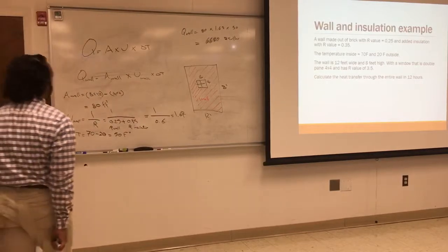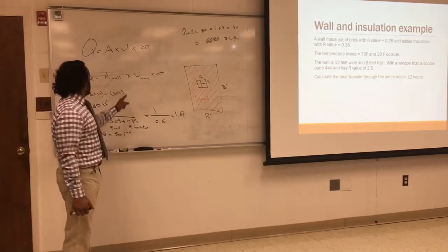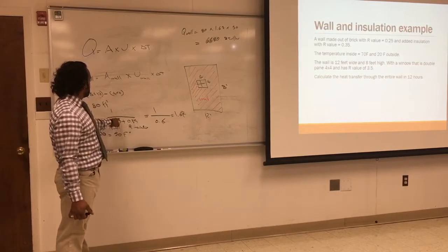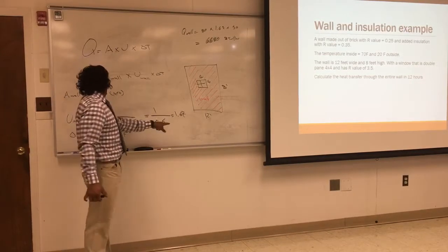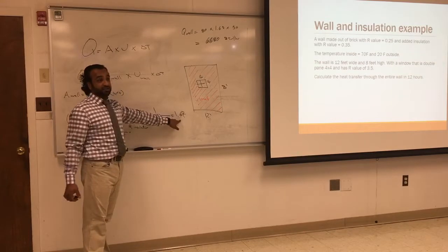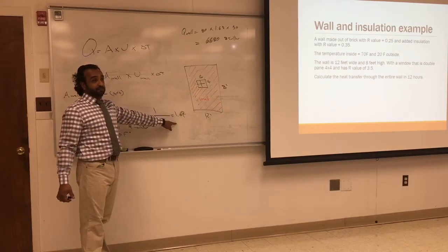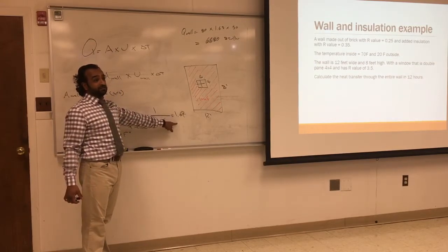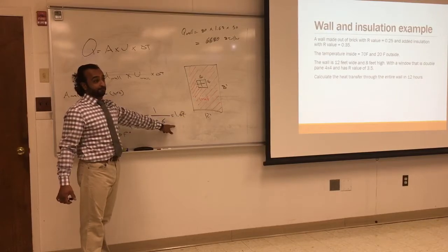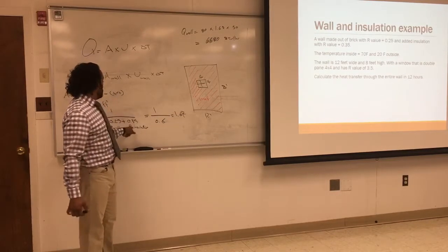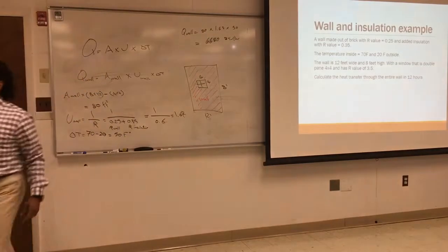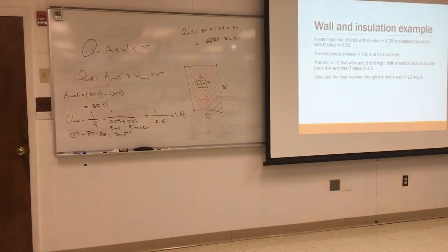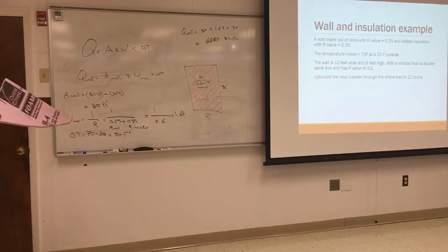If you notice, most of the heat loss is happening through the wall, because my U factor for the wall is still 1.67, which is still high. So we need to add more insulation and find a better solution. 0.35 is really small. They would put R16. Look at this insulation: this is R4, which is 4 times this board.